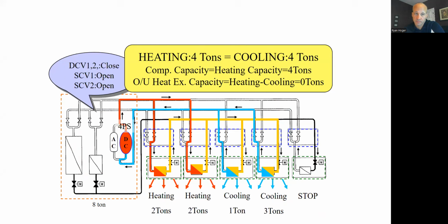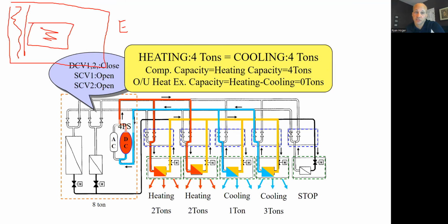Why would I do this? If I go back to that building, right? Here's east, west, north, south, etc. The west zone might need cooling in the afternoon when the sun's beating on it, right? And the interior might need cooling because it always needs cooling. But then the east zone and the north zone might need heating. If I can send the heat from the west zone back over to the guys on the east, why would I not want to do that? Instead of running systems separately for each of them.